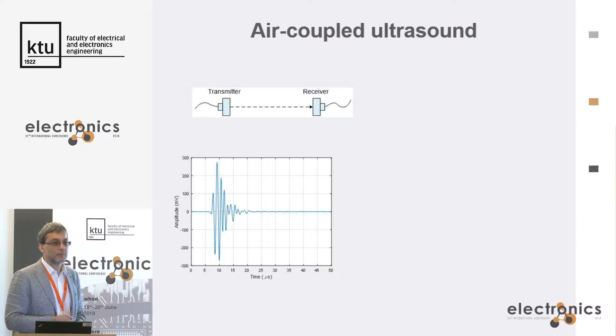This is how the measurement is done: we first measure the signal without the material inserted, then insert the material. This is how the signal looks when it has multiple propagations within the material. By going into the frequency domain and dividing the measured signal by the reference signal, we obtain the magnitude response and phase response. Then, fitting the mathematical model of the material, we get material properties: thickness, density, elastic properties, and even porosity if it's a membrane.